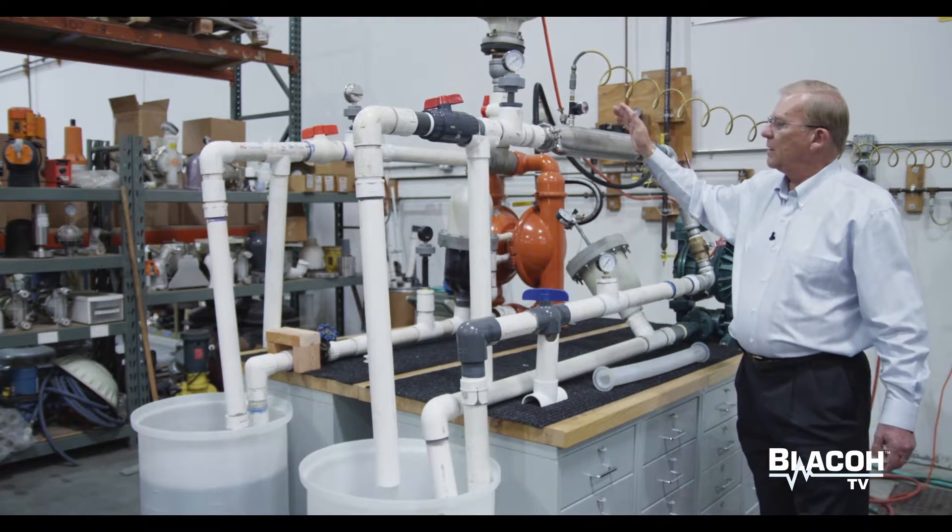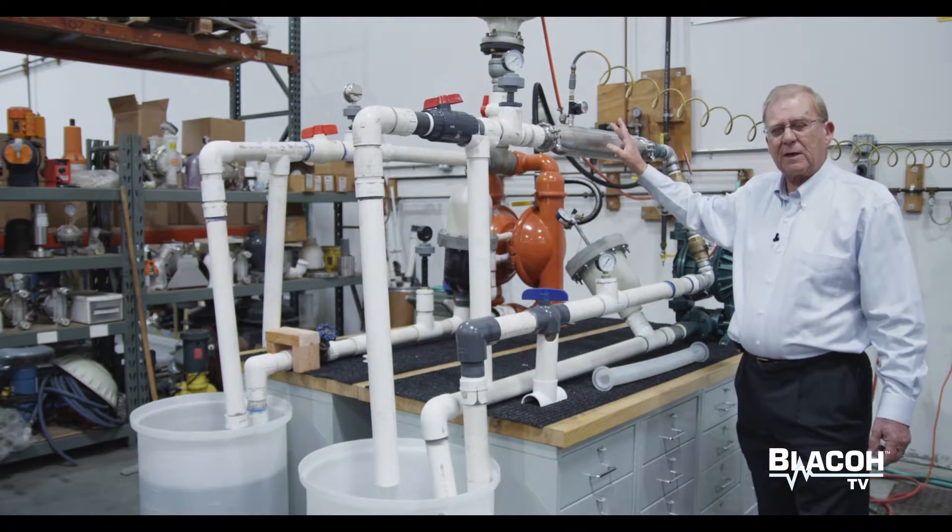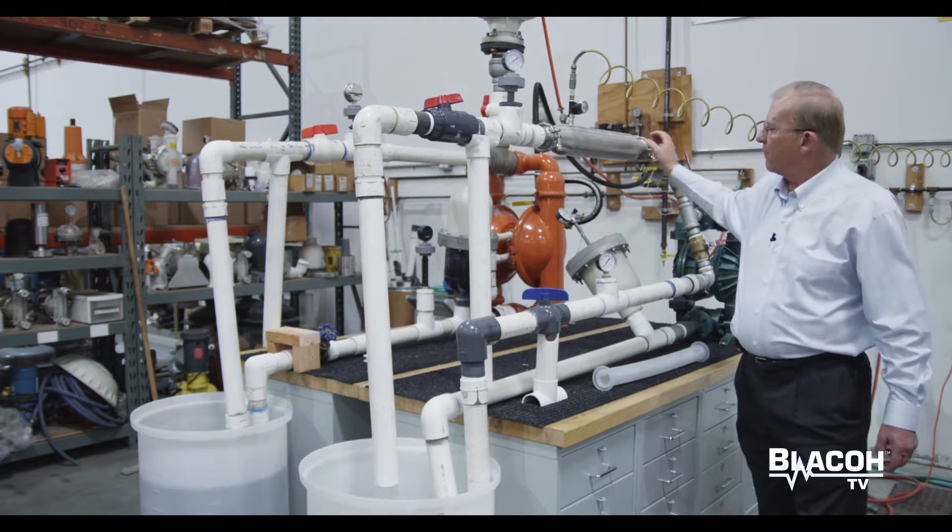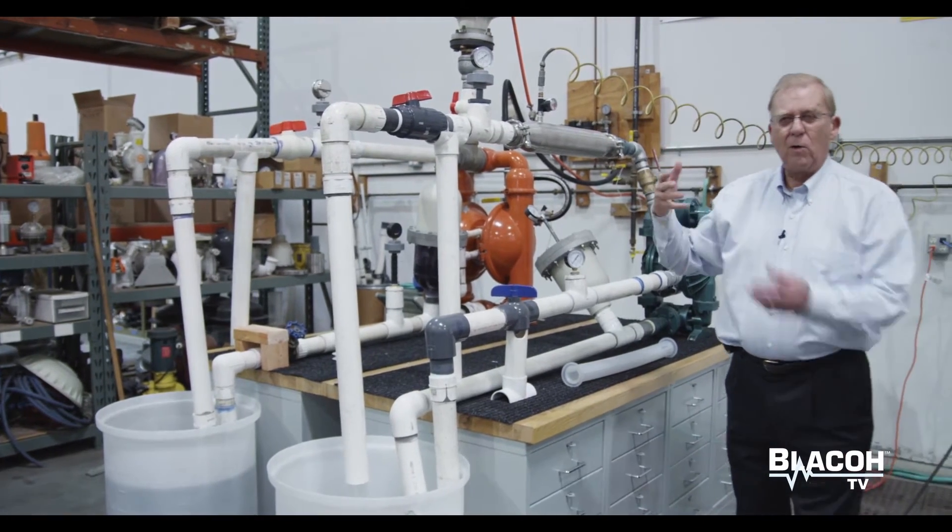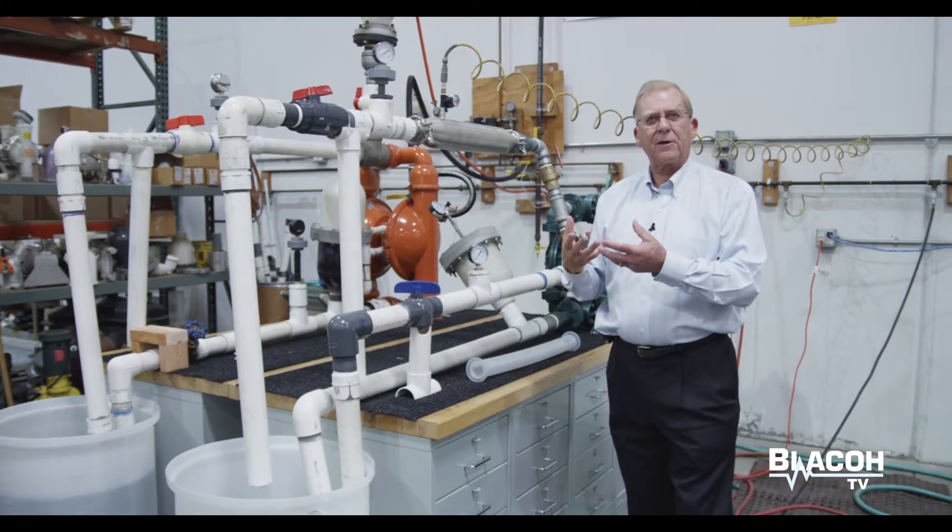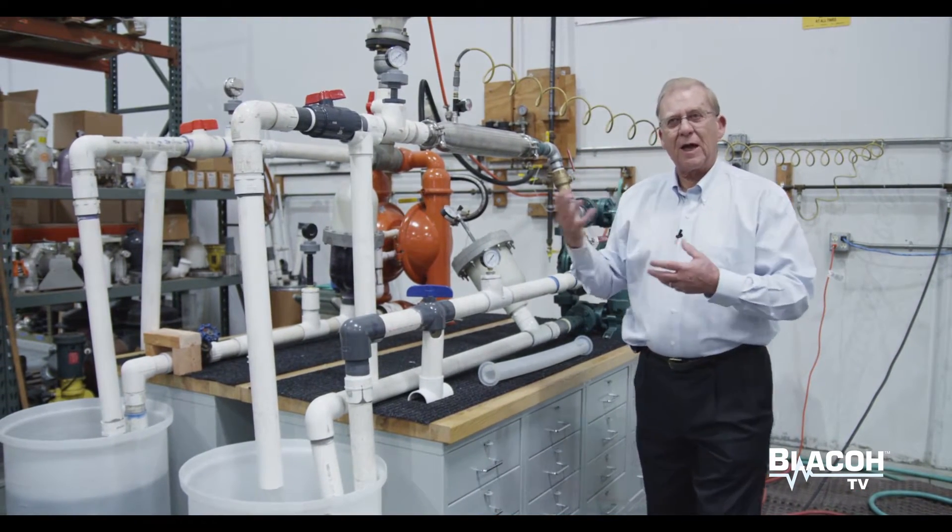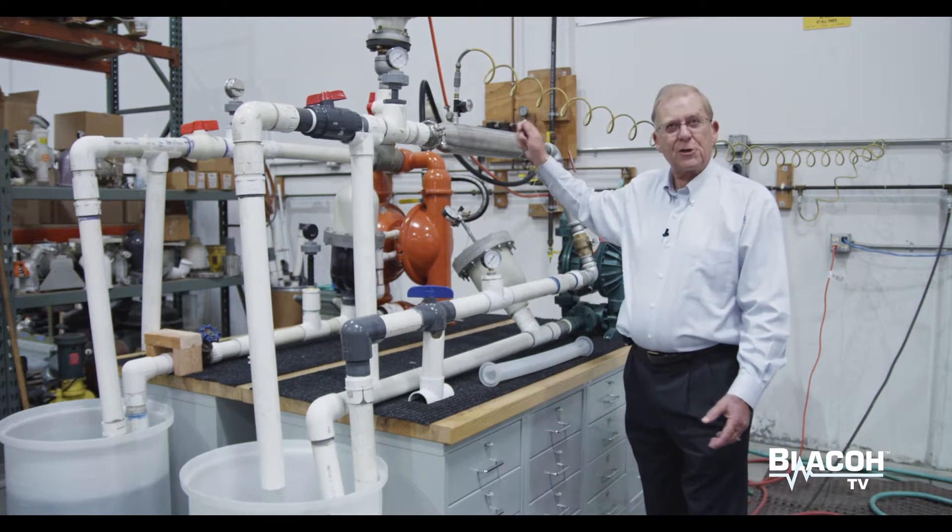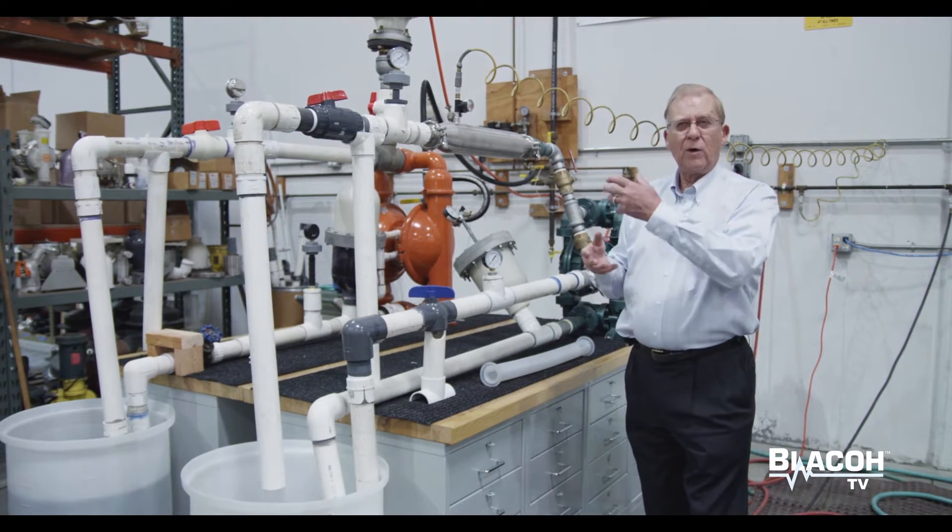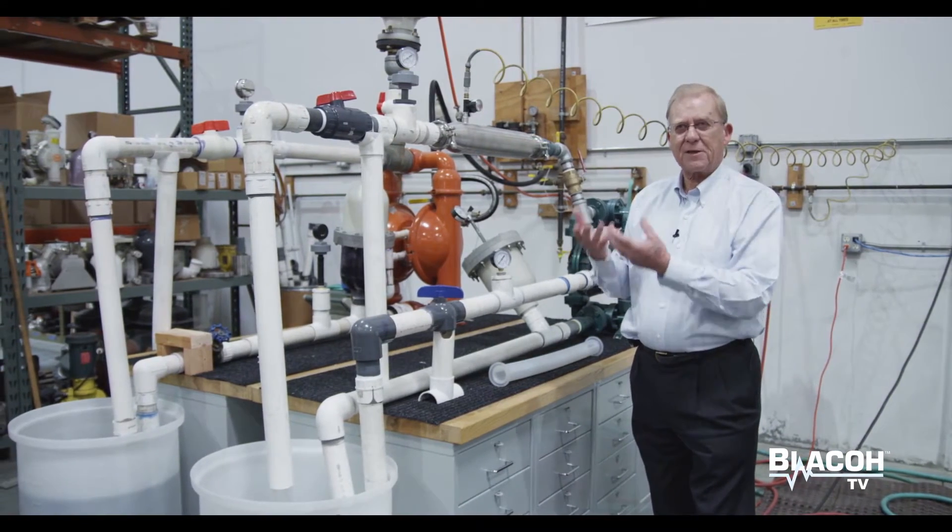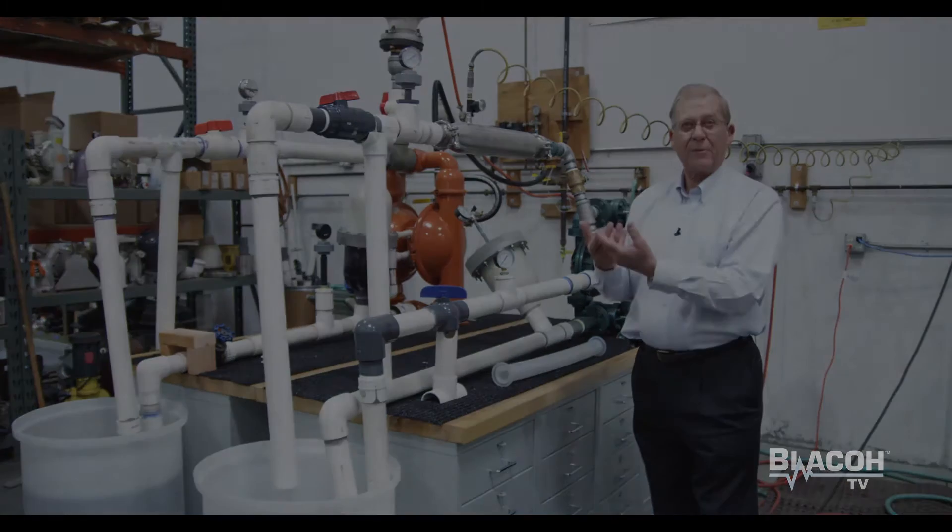This particular model is important because with the flow through design, no holdup of product can occur and therefore in a food or pharmaceutical application, they can stay in production longer than they could with a traditional type of dampener that has a holdup of liquid, like an accumulator.